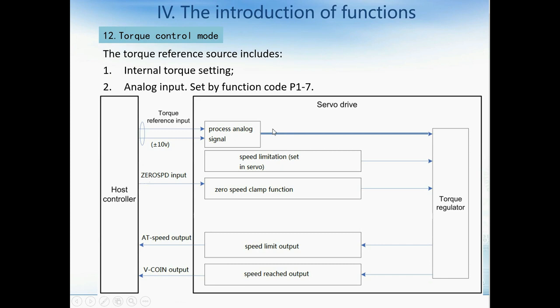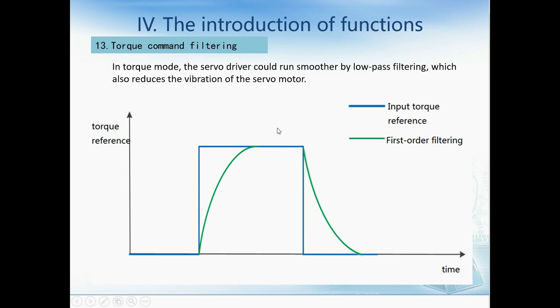Now we talk about torque control mode. The torque reference source includes internal torque setting, and another source is the analog input set by function code P1-7. The torque command also has filtering settings. In torque mode, the servo drive can run smoother by low-pass filtering, which also reduces the vibration of the servo motor. The first-order filtering makes the curve smoother.